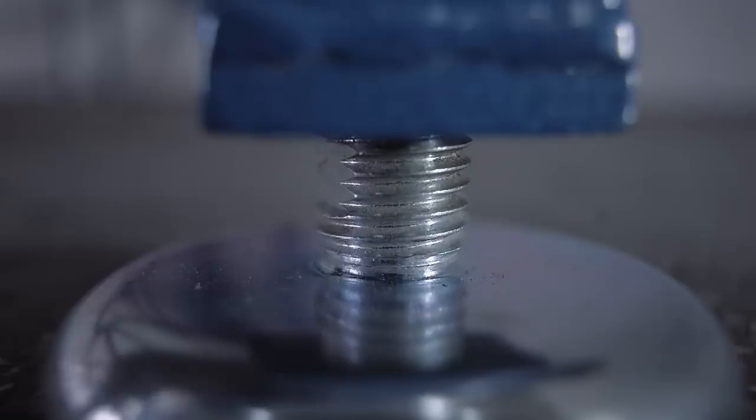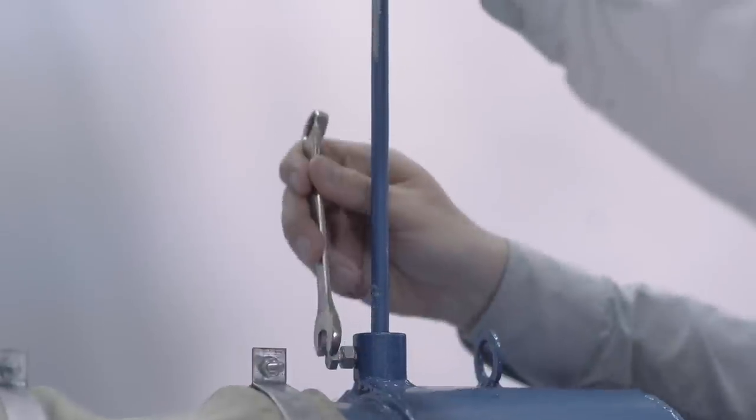If you use a bag to collect dust and small product particles from the cyclone, secure the bag on the pipe of the discharge valve. If necessary, adjust the angle of the longitudinal axis of the cooler device through the supports. Close the gate of the pipe. Run a short idle start, no more than one minute. Make sure of proper operation and the absence of extraneous sounds.